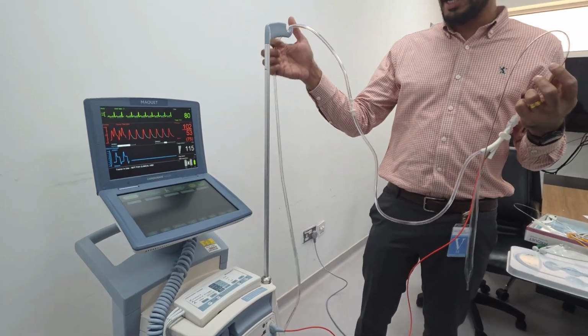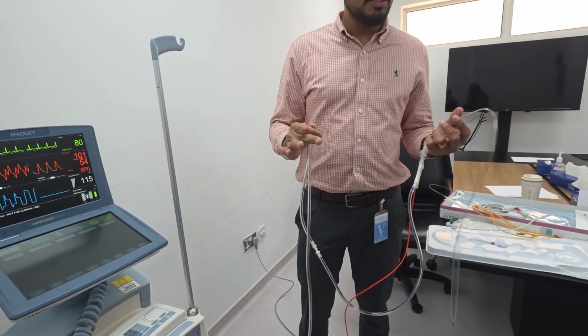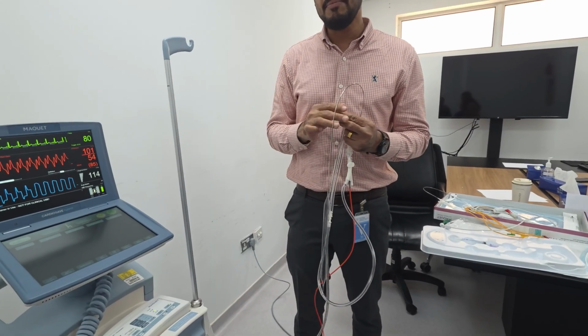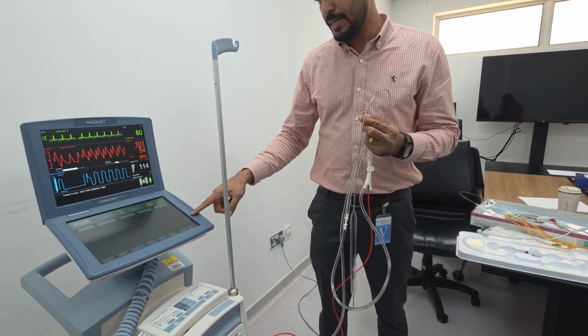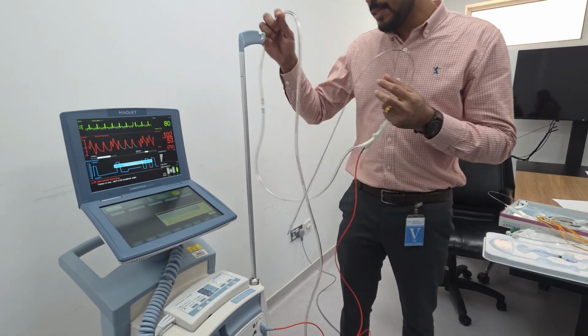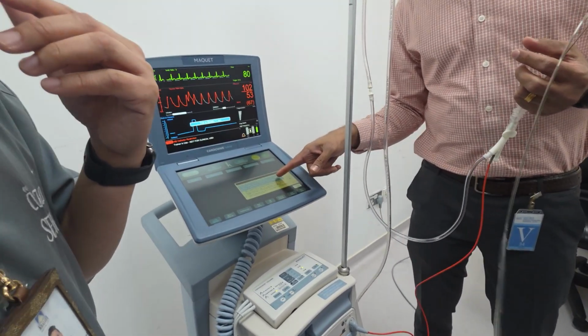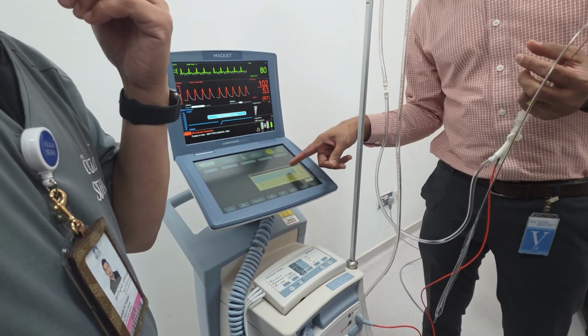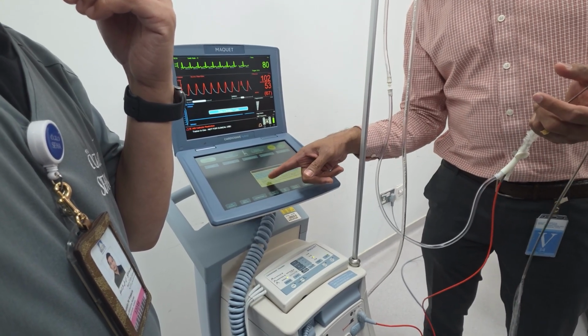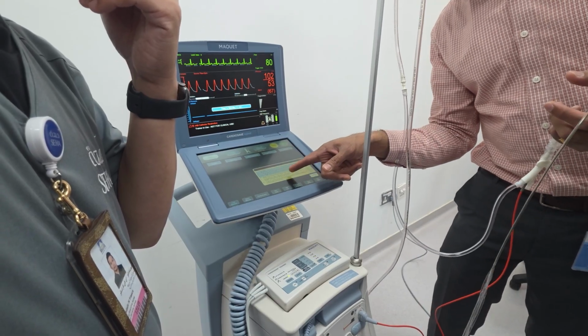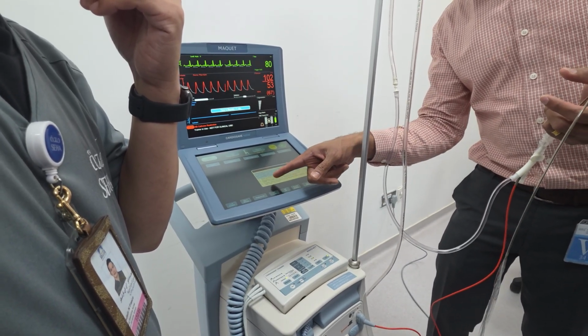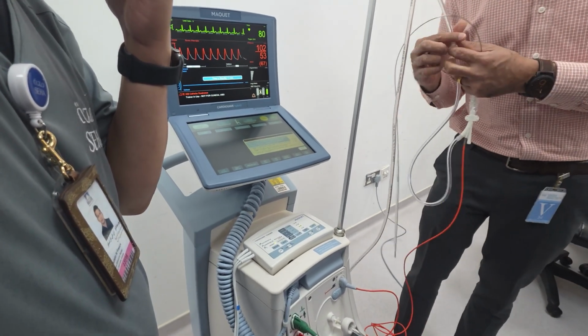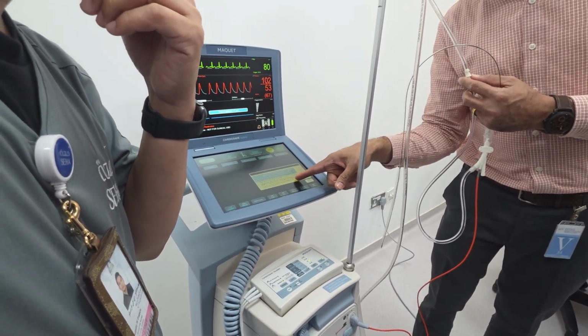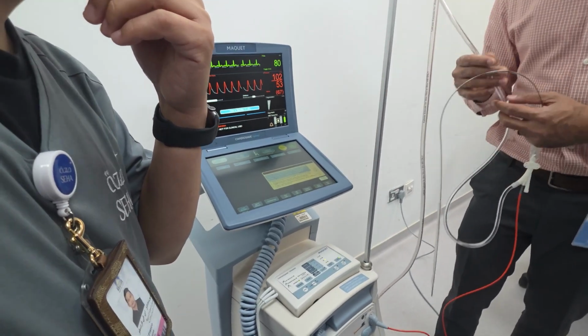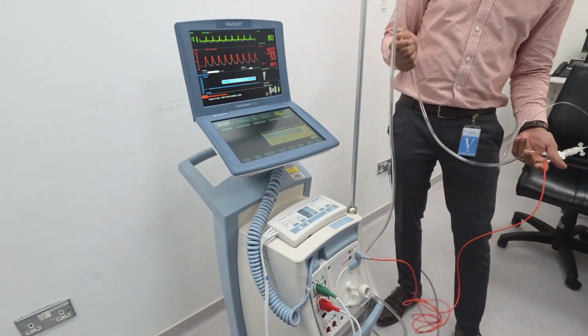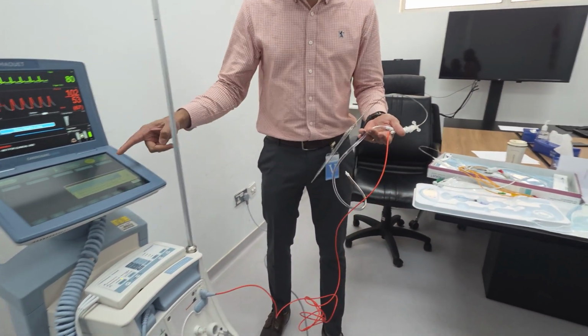I will show you the instruction on what to do again. It's a new machine, but the same as the CS300. Whenever you have an alarm, there is a help icon here. When you move it, see: check for evidence of blood in the tubing, and if there is no evidence of blood, you can proceed with the next step I discussed. But stop pumping. It clearly means to disconnect the catheter extension tubing from the IABP console from here, and you need to clamp the extracorporeal tubing between the Y connection fitting and the male connector. This is the Y connection, and this is the male connection. You need to clamp it here. So that gives the clear indication.